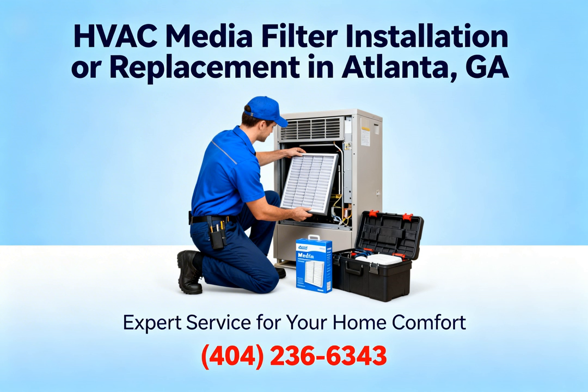Right, standard AC stuff. But if that dense filter is blocking the airflow, there isn't enough warm air moving over the coils. Without that heat transfer, the refrigerant never boils. It stays liquid, and its temperature drops well below freezing. And because we already established that Georgia air is thick with humidity? Oh, the moisture in the sluggish air hits that sub-freezing metal coil and immediately condenses into frost. Just freezes right on contact. Instantly. And within hours, that frost builds into a solid block of ice, completely encasing the evaporator coil.